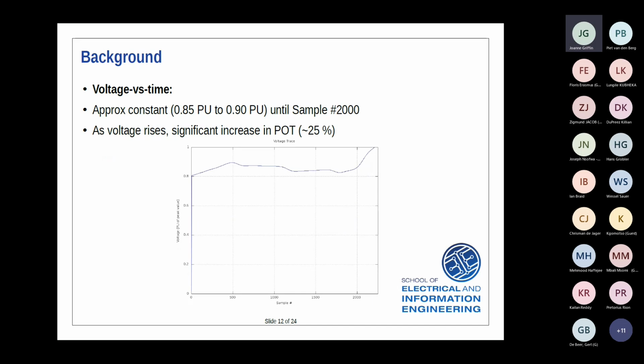And then if we look at the voltage, so this is the voltage recorded during the same test, relatively constant. Now, just to give you some background, that's controlled by a test bed operator who's got this big synchronous generator next to it, and he's controlling the field winding on that synchronous generator. And obviously, as the machine runs from just after it's been plugged, where the slip is 2, massive currents going into the machine to break it, you can see that the voltage is quite difficult to regulate. It's going up and down, and he's doing his best to regulate that voltage. And then towards the end, as the machine starts accelerating, the current reduces quite significantly, and you can see the voltage comes up to full rated value.